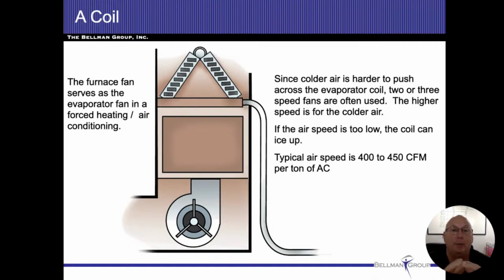So most of the modern furnaces, they're going to have multi-speed fans on them. Sometimes 2 speeds, sometimes 3 speeds, sometimes variable speed. All right. But because colder air is harder to push through the ductwork, we're going to want to increase the airflow when we're running in the air conditioning system. So as you're checking your airflow, and this is a lot of problems you're going to run into, even with new construction homes, people end up undersizing ductwork. It may be correct in the math, but it just doesn't work.